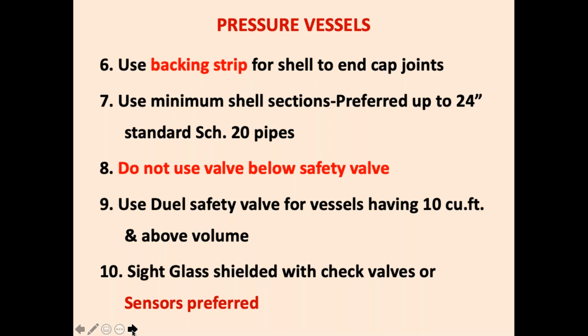Use minimum shell sections. I've seen many places with receivers and shell and tube condensers that have 3, 4, or 5 joints on a 20 feet long receiver. There are 4 pieces or 5 pieces. Why do that? Use a single plate, or at the most one joint if the receiver is too long. So, a very important point: do not use a valve below a safety valve.